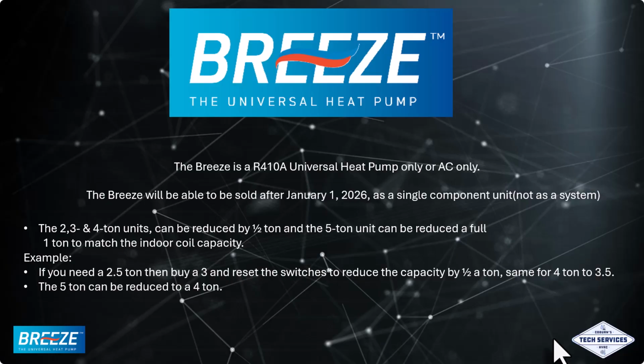The 2, 3, and 4 ton units can be reduced in capacity by 1/2 a ton, and the 5 ton can be reduced a full ton to match the indoor coil capacity. Example, if you have a 2.5 ton unit, then you buy a 3 ton, reset the dip switches to reduce the capacity by 1/2 a ton.